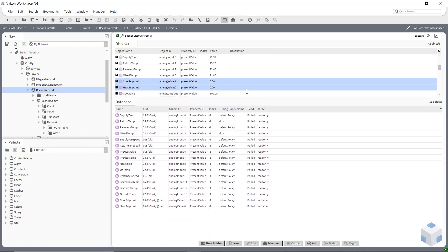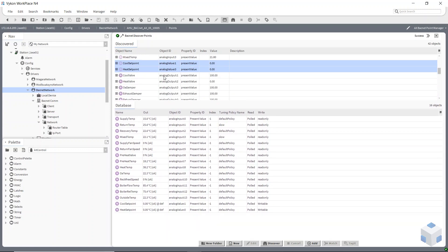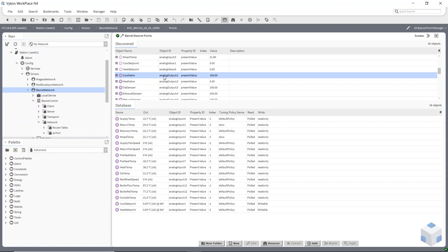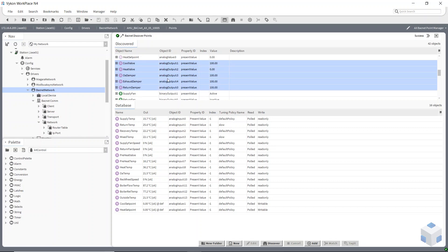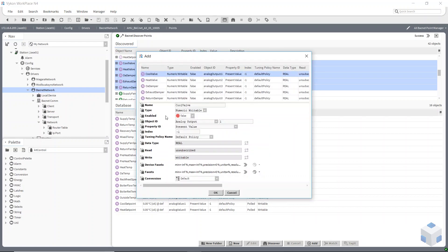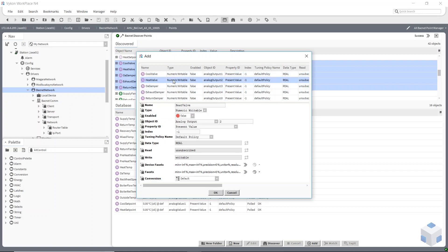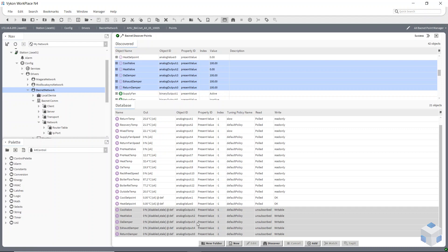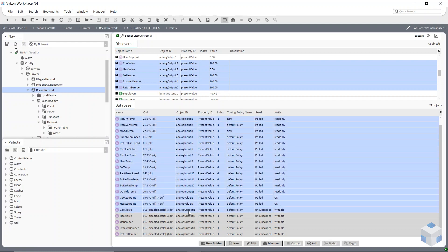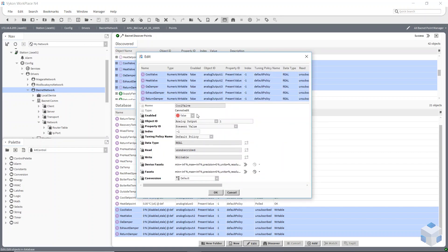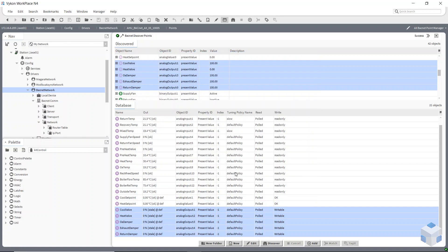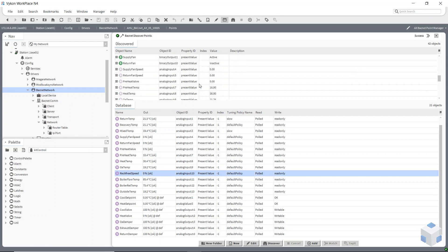So what you need to make sure of is all your points in your database are all healthy. You don't want to see any points which are disabled or which would be grey. So if I now bring in my analog outputs, drag them down, so you can see they're disabled. So if I bring them all in, disabled, you can see I'll get grey line. So if you get that you can then just highlight them all again, click on edit at the bottom and then you're presented with this wizard again and you can just go and click on true and they're all healthy. So you carry on just adding all your points in the same fashion, just making sure they're all healthy once you get them into there and make sure that they're writable if they're meant to be writable. Again you can enable this column and you'll be able to see in your table.